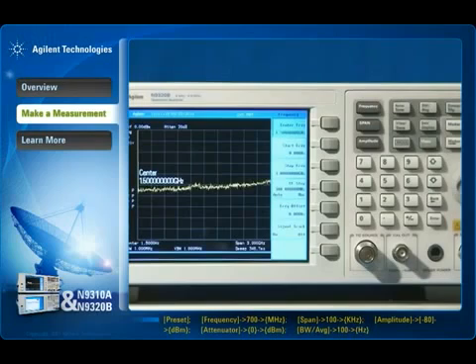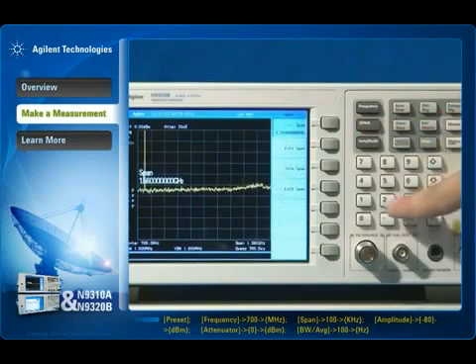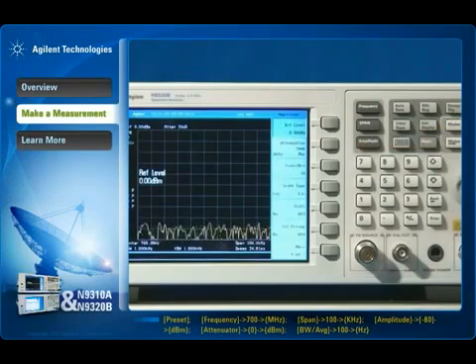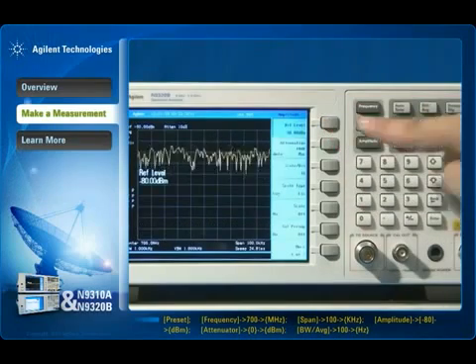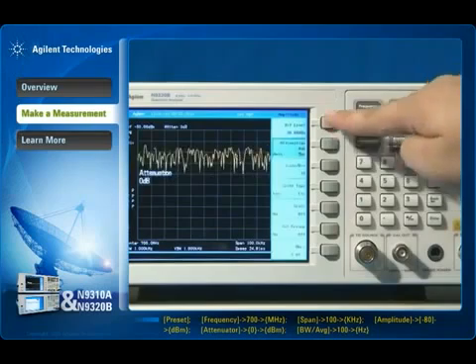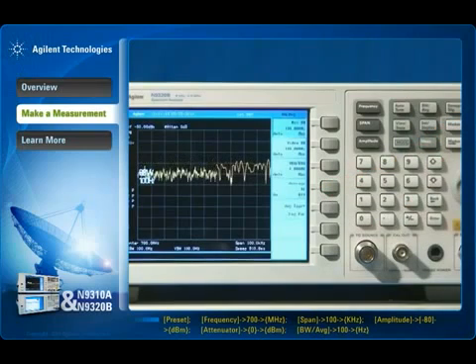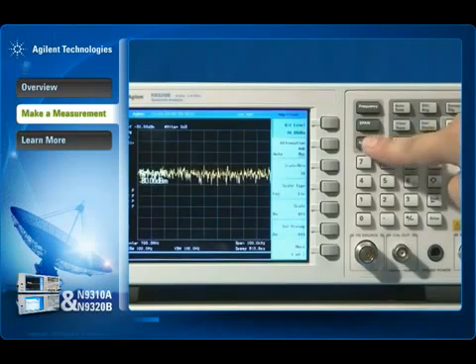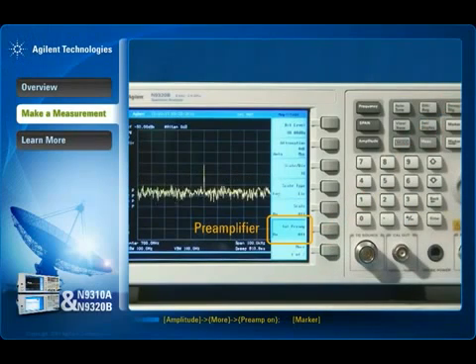Set the frequency, span, reference level, and attenuation as shown. In the resulting screen, it is still hard to see the signal clearly. To address this, when you enable the preamplifier, the noise floor decreases and the low level signal is then easily detected.